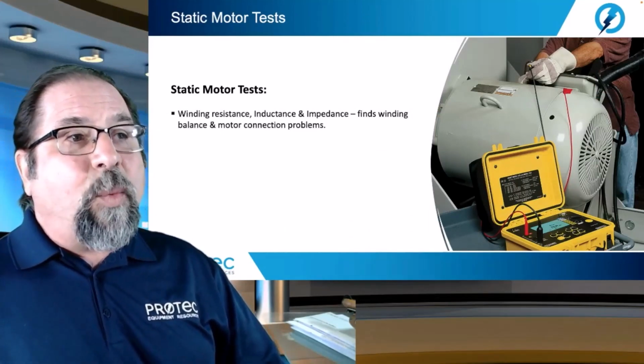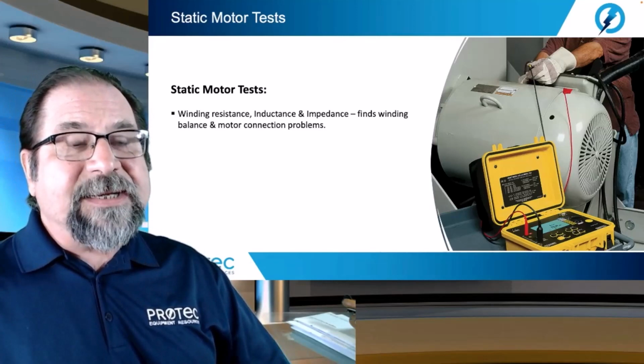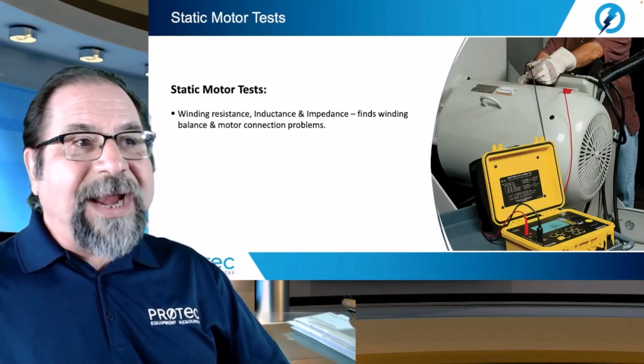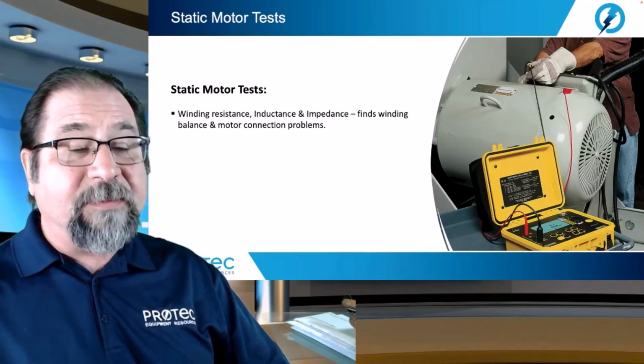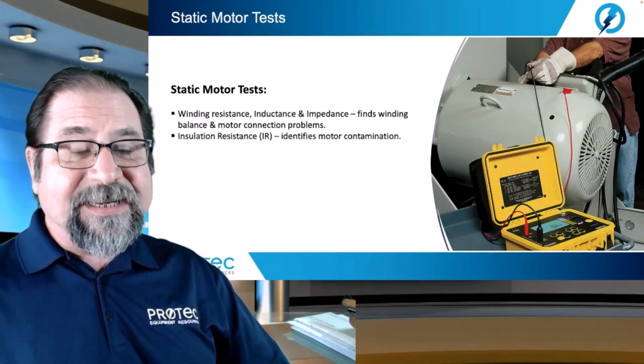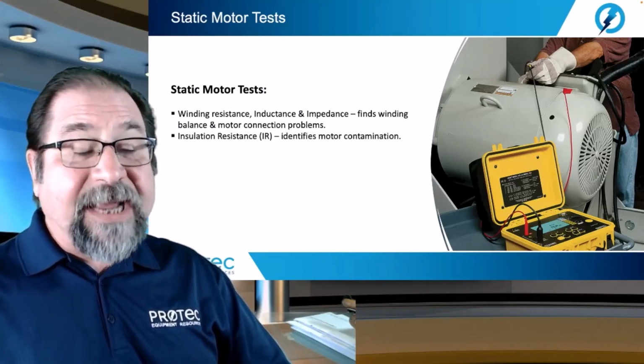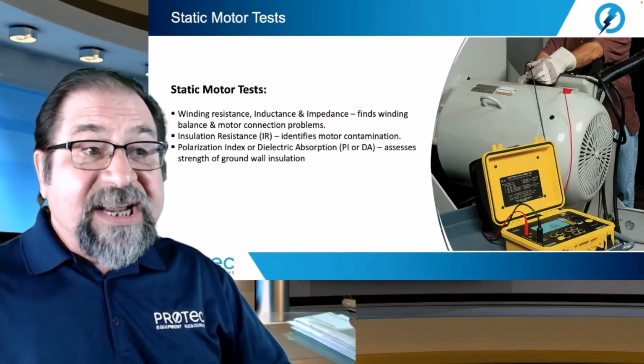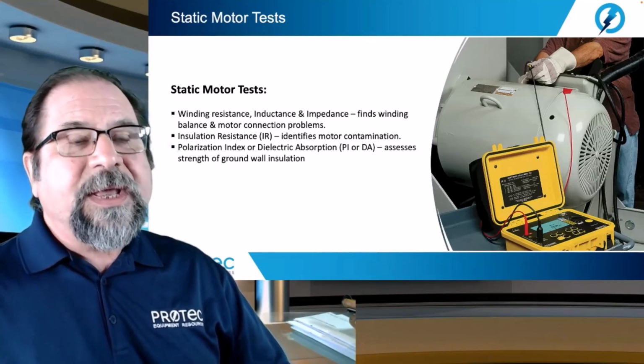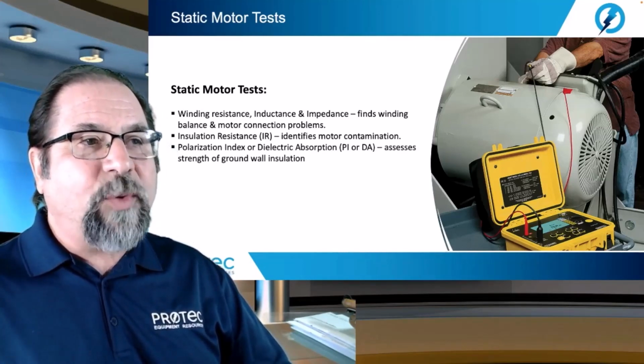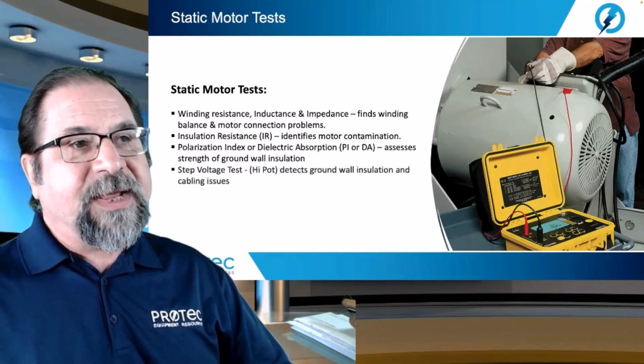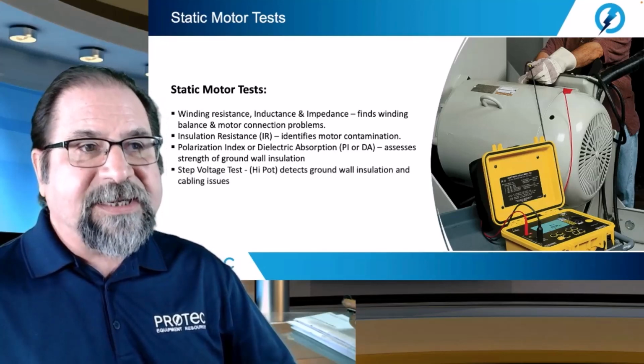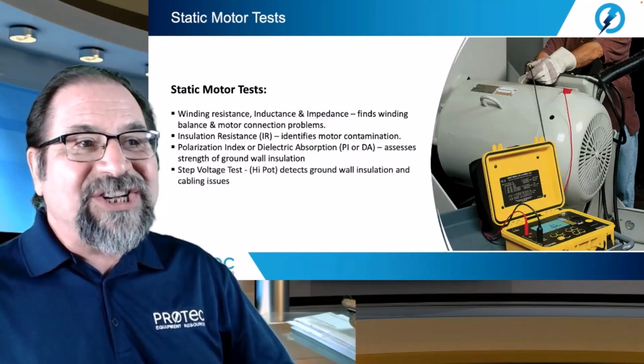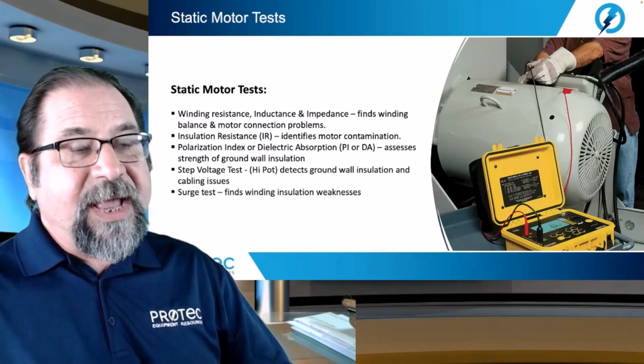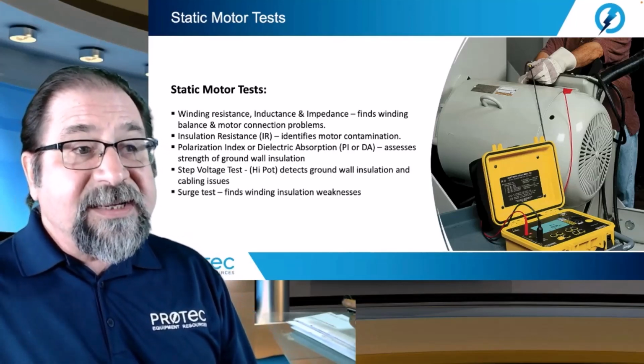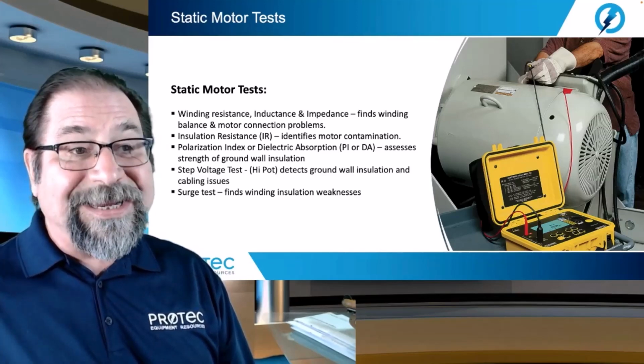So, winding resistance, inductance, and impedance. These types of tests find winding balance and motor connection problems. Insulation resistance. This test identifies motor contamination. Polarization index or dielectric absorption. These tests assess strength of ground wall insulation. The step voltage or high potential tests. These detect ground wall insulation and cabling issues. And also the surge test. This is used to find winding insulation weaknesses.